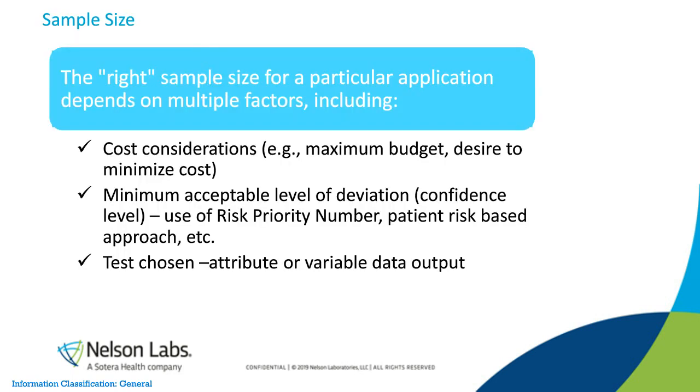A couple other things you're going to want to think about when you pick the sample size. What is the right sample size? There are many factors that go into picking it besides the statistics. For example, what are the costs? If you have a device that's going to cost $30,000 to develop and manufacture, using a sample size of 29 for every single test isn't going to be appropriate.